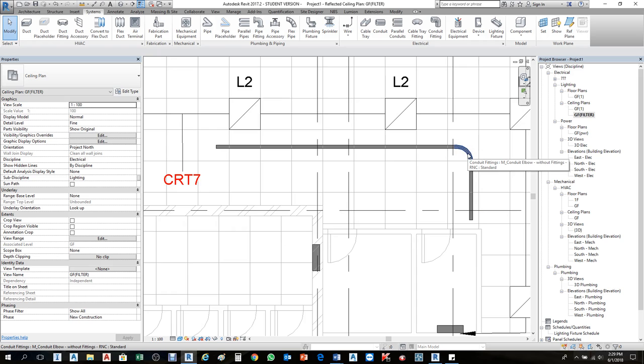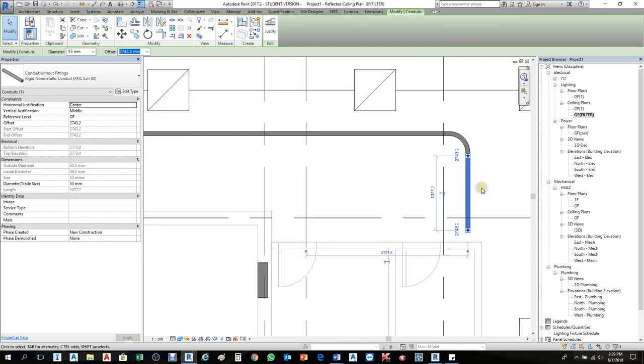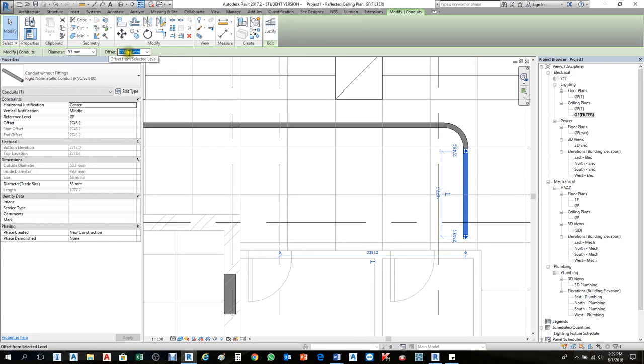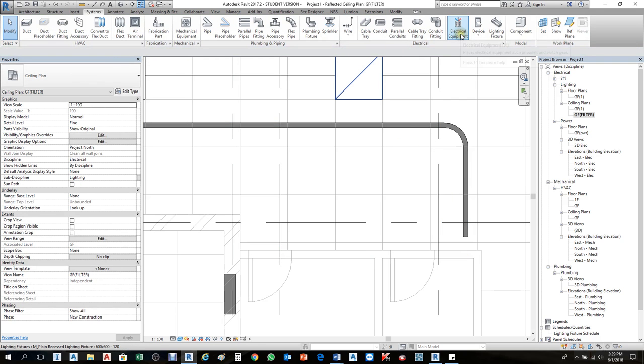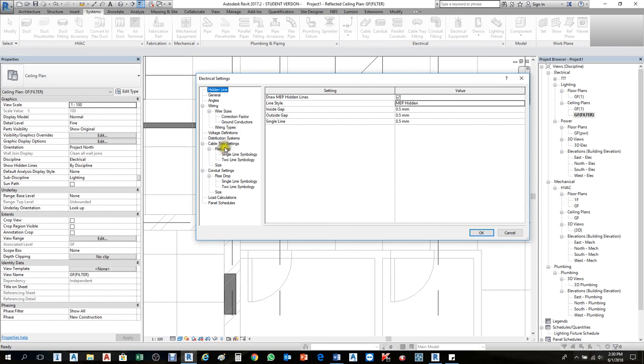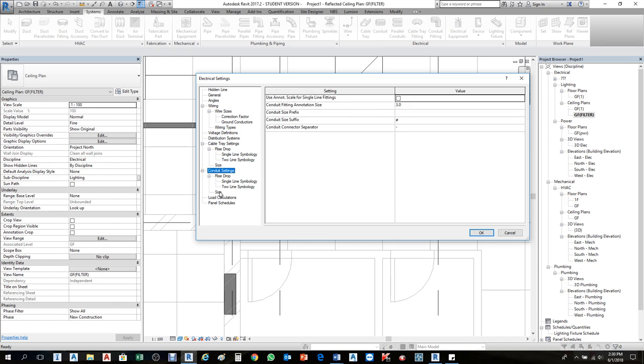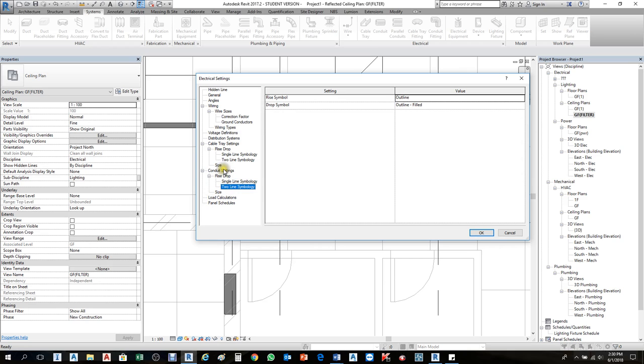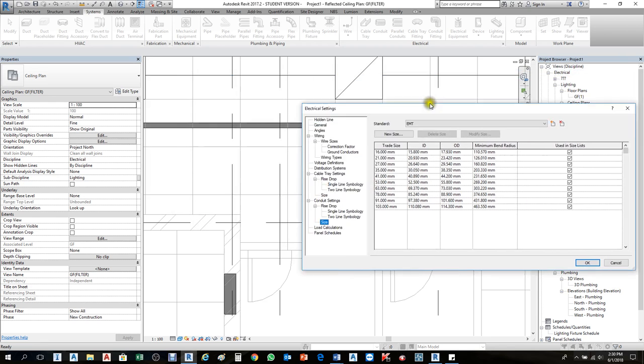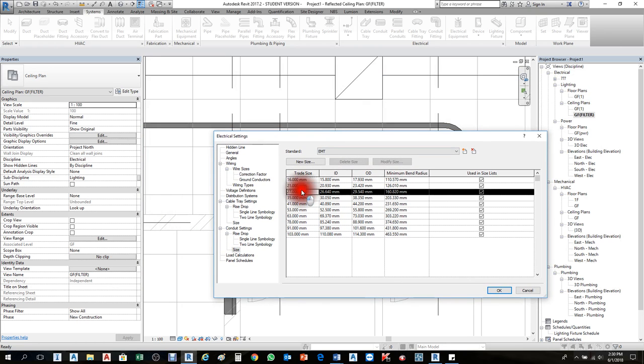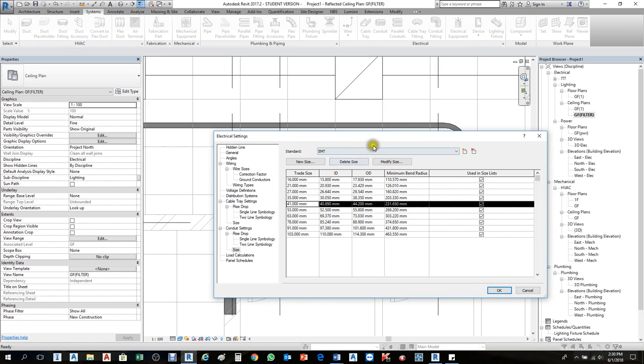For conduit settings, go to conduit settings again. By default, if you click on conduits, the starting size is around 27mm. Go to the Electrical setting, click the arrow dropdown, then go to Conduit Settings and then Sizes. From here you can change the size of the conduit. We have EMT, IMC, RNC, and other types of conduit available.